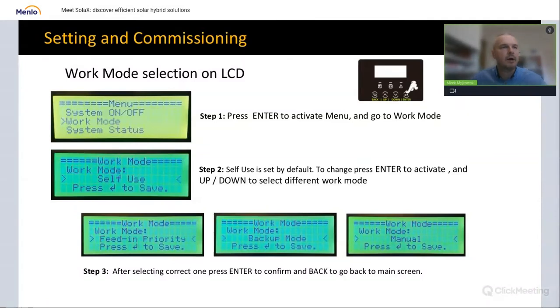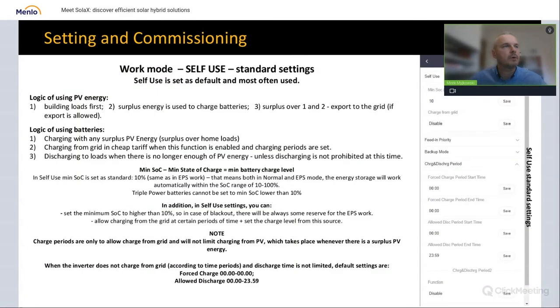So what is the logic of the work modes? The most commonly used and set as default is self-use. The logic is: building load first, so PV energy goes to the building first, then the surplus energy is used to charge batteries, and if the batteries are full and the building has no more needs, the surplus will be exported to the grid, if export is allowed.